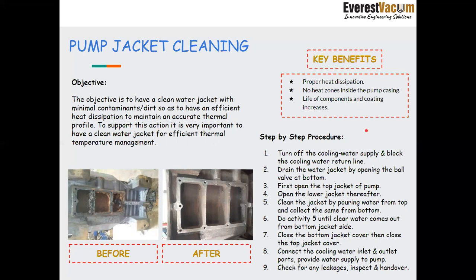And how is it to be done? Turn off the cooling water supply and block the cooling water return line. Drain the water jacket by opening the ball valve. There are pre-fitted ball valves at the bottom. First we need to open the top jacket of the pump, then open the lower jacket thereafter. Clean the jacket by pouring water from the top and collecting it from the bottom. This needs to be done until clean water comes out. Once it is done, we can install the inlet and outlet lines again and connect it towards the process. We need to check for any leakages, and if there are none, we inspect it and then the pump can be handed over to production.